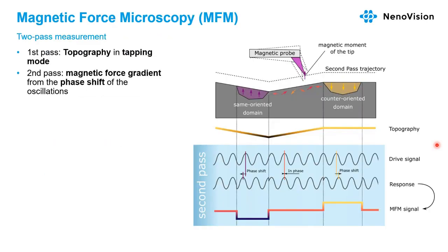So how do we measure? We measure MFM in a two-pass technique. In the first pass, we measure the topography. In the second pass, the probe repeats the topography trajectory and measures the phase shift of the probe oscillations, which is now the MFM signal.